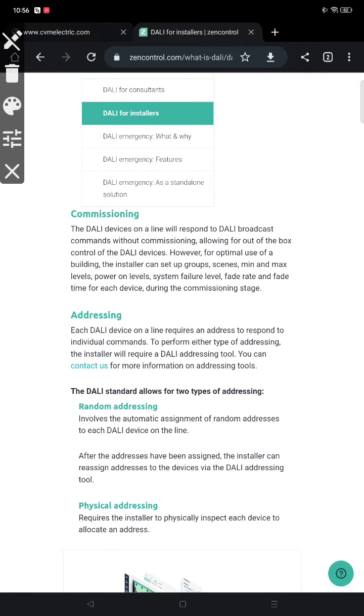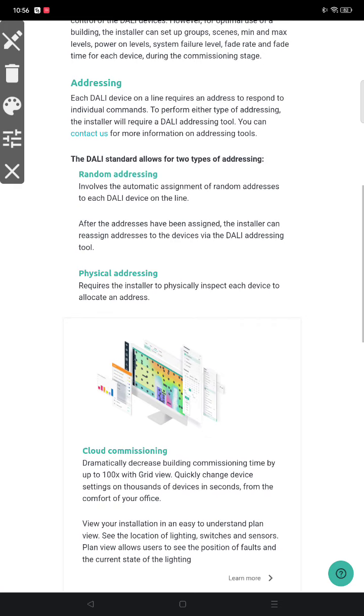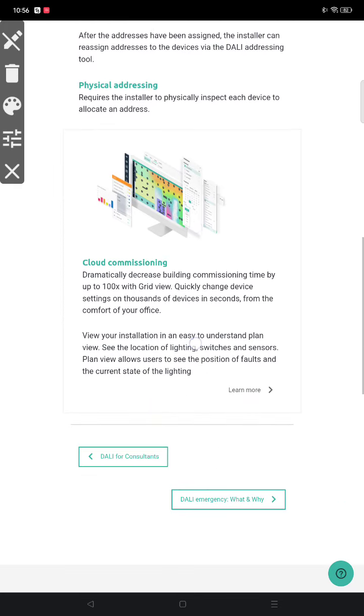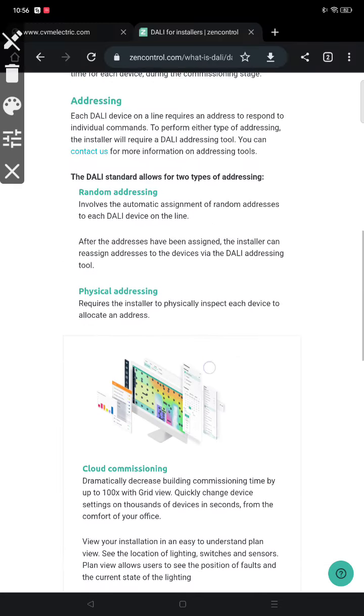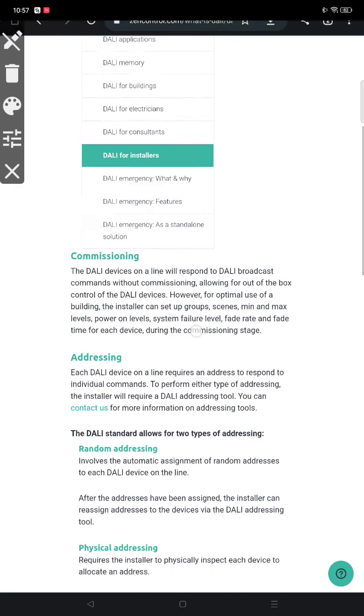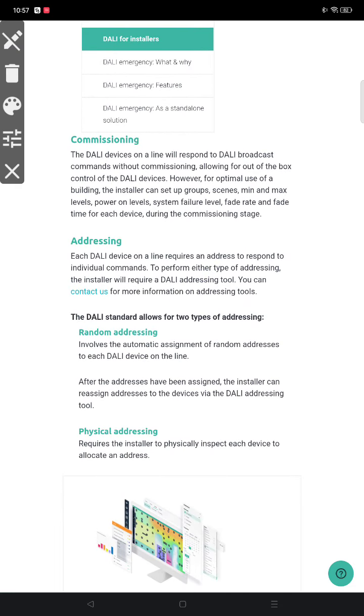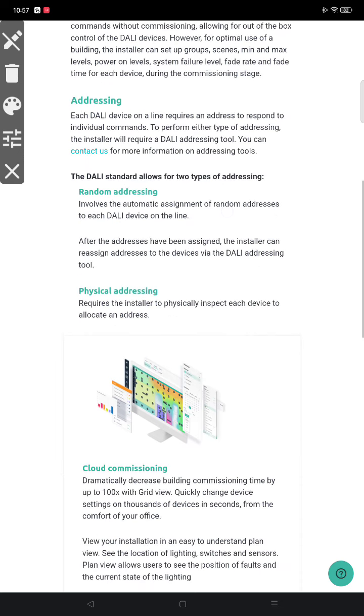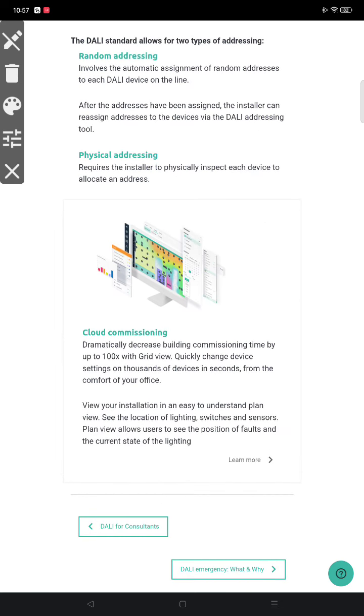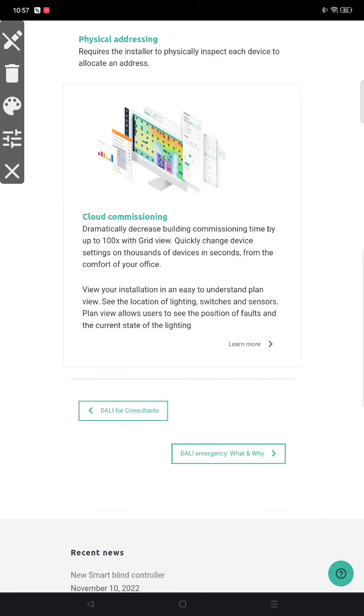Okay, commissioning, addressing, random addressing, then physical addressing, cloud. There are a few things. Each DALI device on a line is required to have an address to respond. Physical address. Two types of addressing: random addressing and physical addressing. Cloud commissioning. Okay, dramatically decrease building commissioning time by up to 100x.